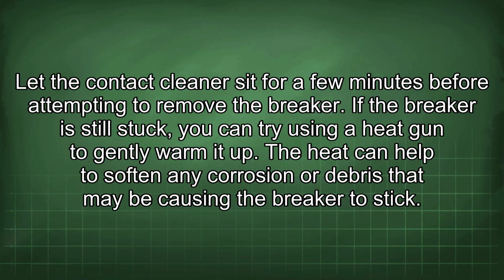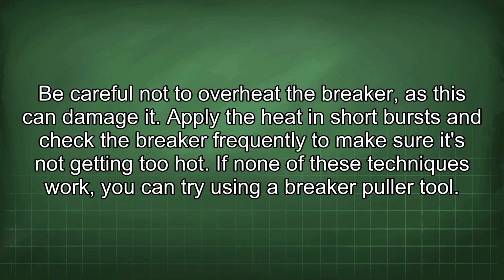The heat can help to soften any corrosion or debris that may be causing the breaker to stick. Be careful not to overheat the breaker, as this can damage it. Apply the heat in short bursts and check the breaker frequently to make sure it's not getting too hot.